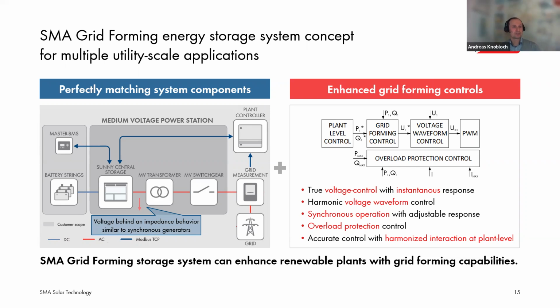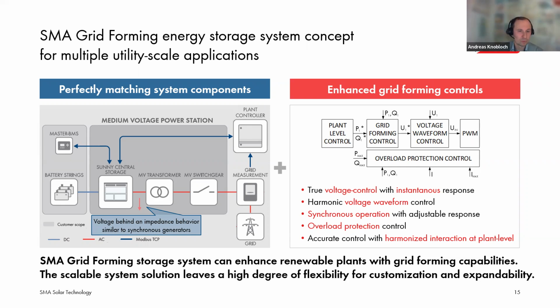On the other side of the system, we provide our enhanced grid forming controls that let the system behave as a true voltage source with an instantaneous response, where we have a voltage waveform controller that enables forming the voltage waveform at the inverter terminals. It enables synchronous operation with adjustable response that I will explain on the next slide.